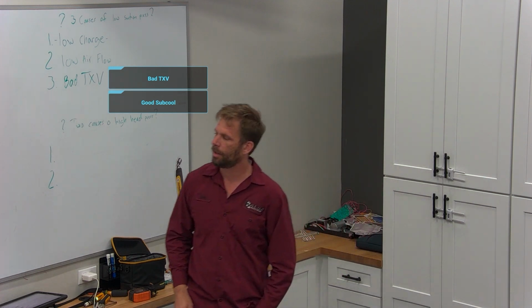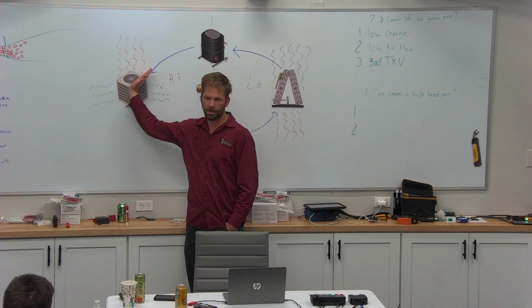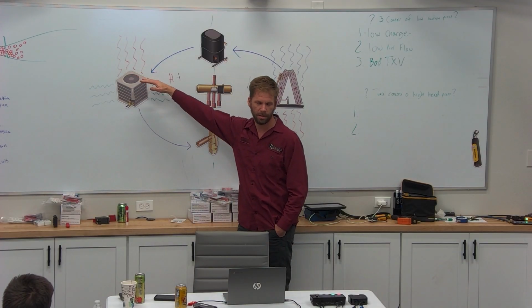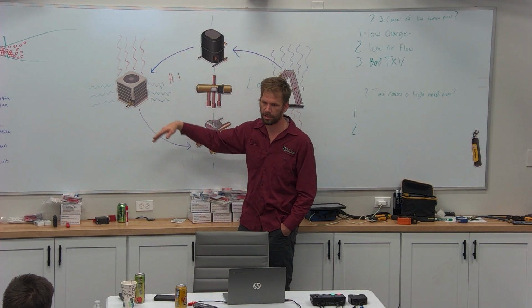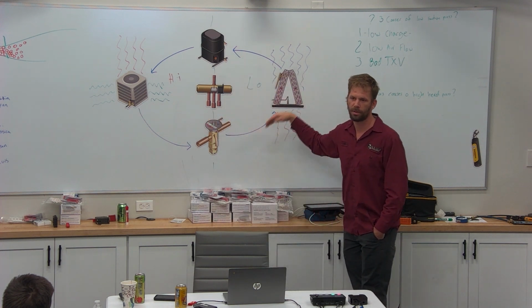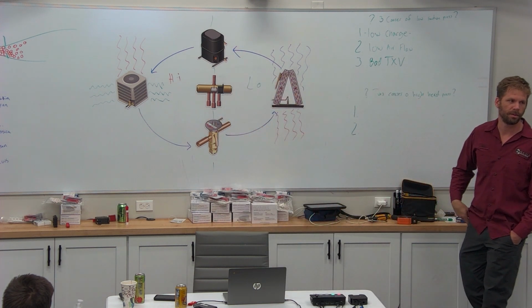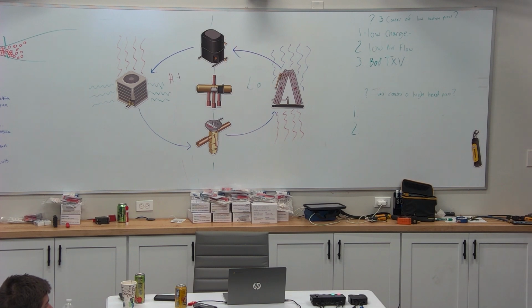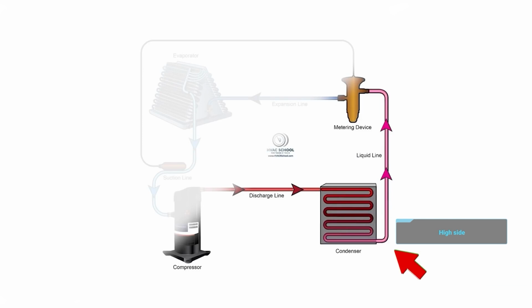The bad TXV has good subcool because it's restricted here, but it's still backing up. Nice high pressure, plenty of refrigerant in here. So we're still doing our job over on this side. It's this side that's restricted and dropped down and not doing its job. Now, low refrigerant. What are we going to notice when we hook up on our high side and we have low refrigerant charge?